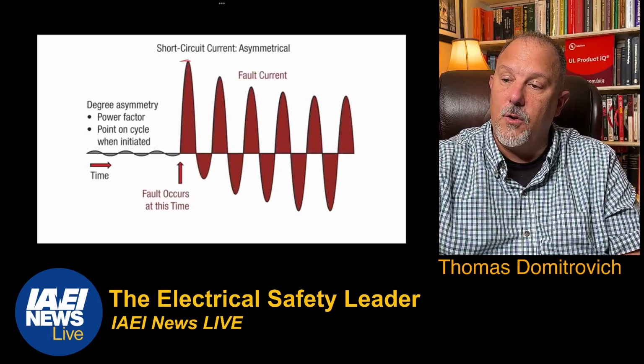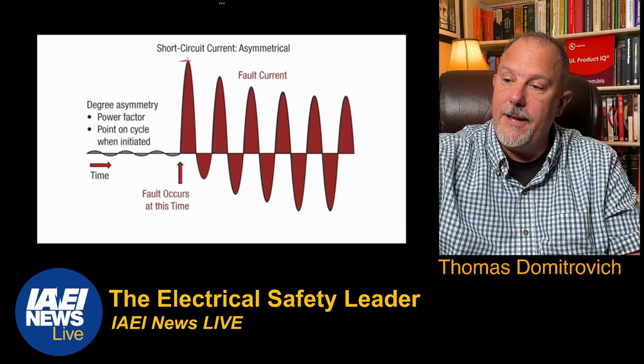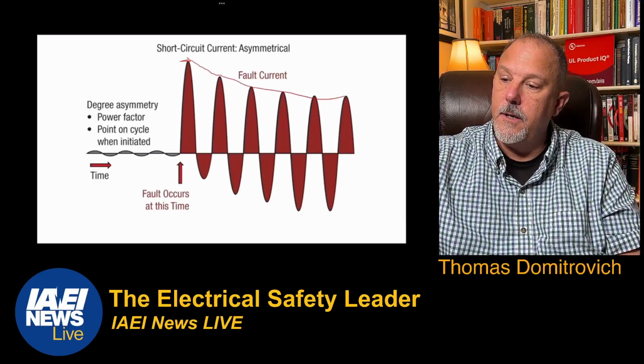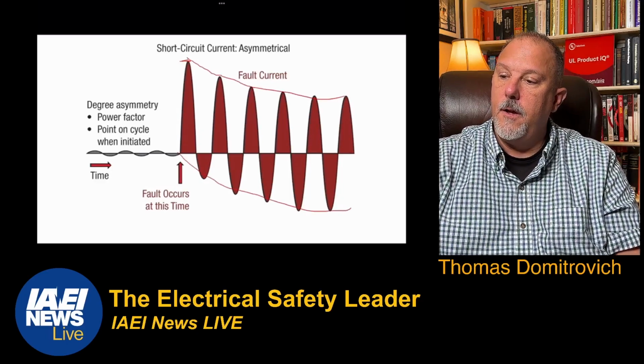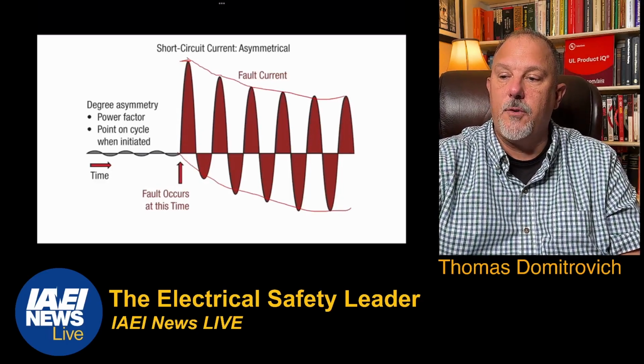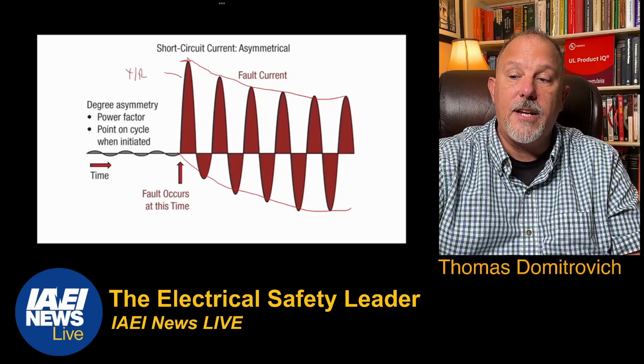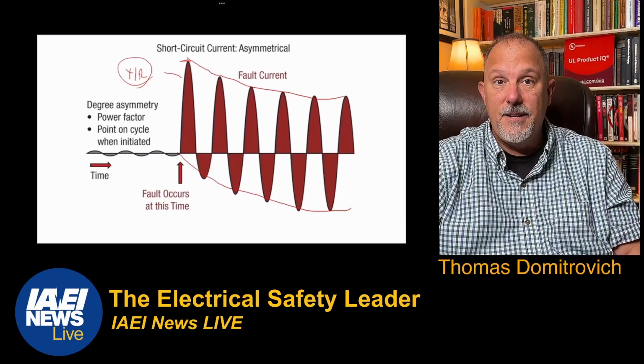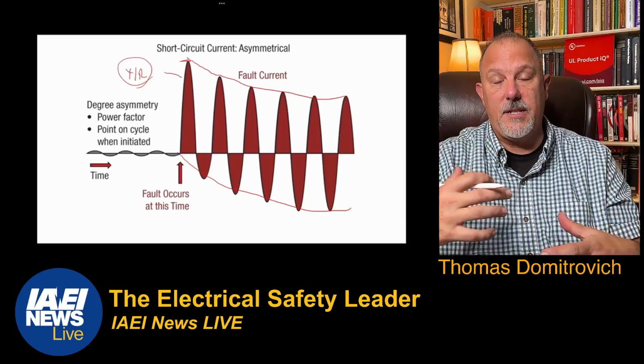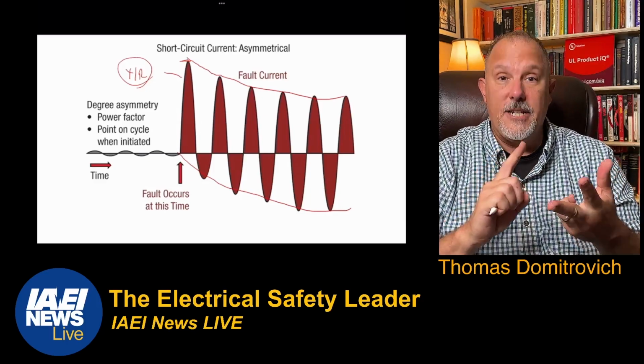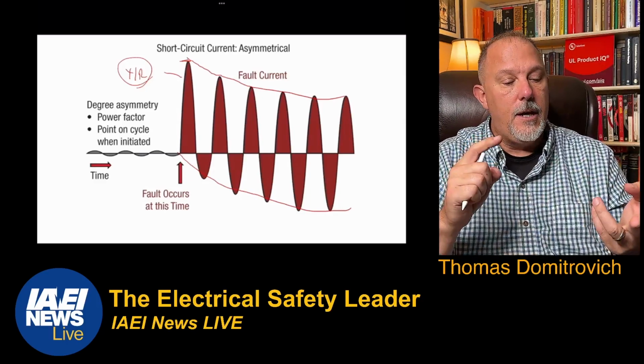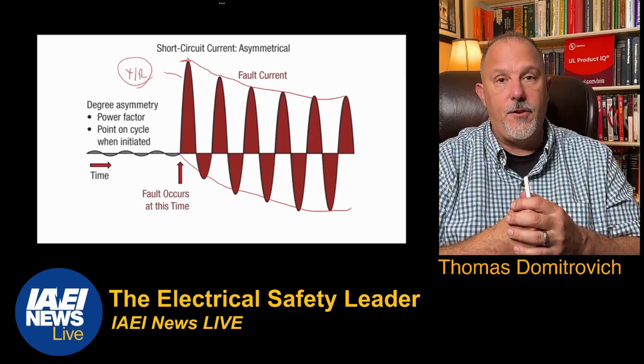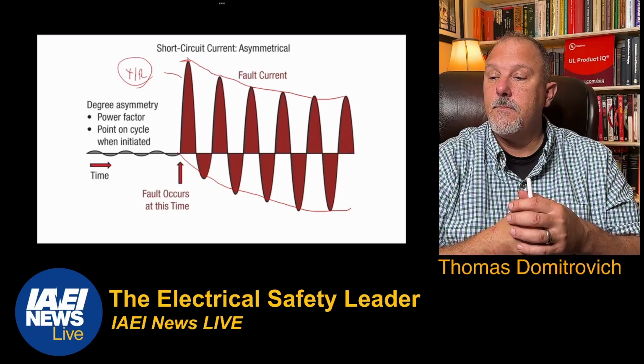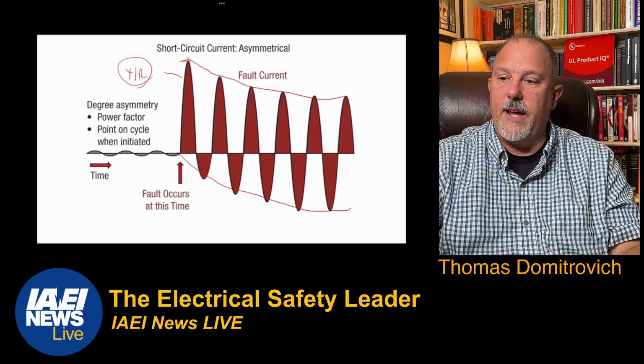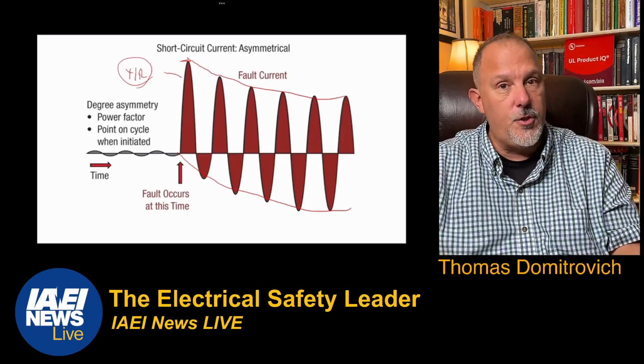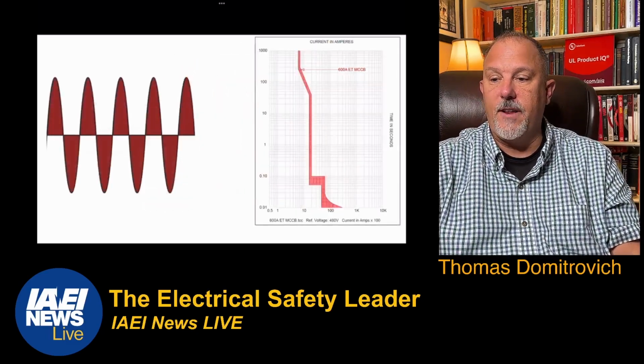So this first half cycle, what you have here is what we call a DC decay. Right? So this first asymmetrical, this is going to be determined by what we call the X to R ratio of the circuit, of the system. That is the impedance to the resistance. What are the X's? Transformers, conductors have X impedance, any caps, things like that. And then the resistance is primarily your conductors. But when you first initiate a fault, that first half cycle is a doozy. It's the most you'll see in the power system for any fault conditions.